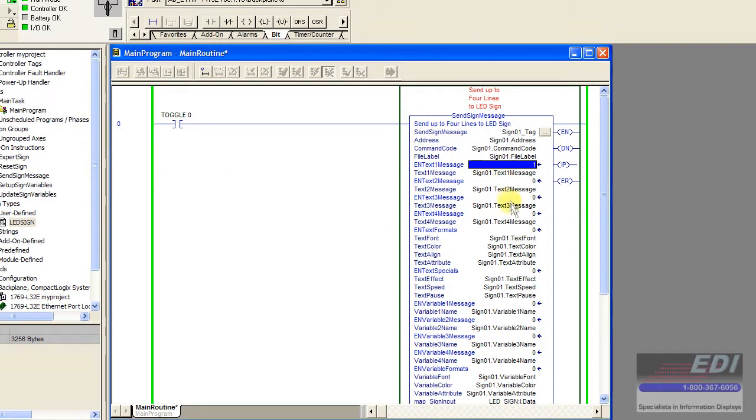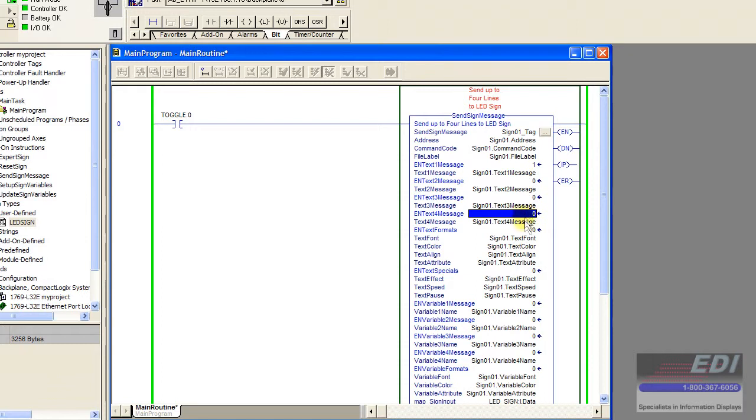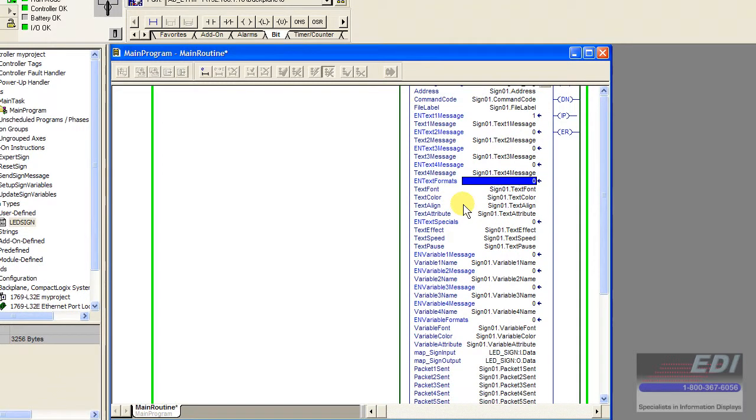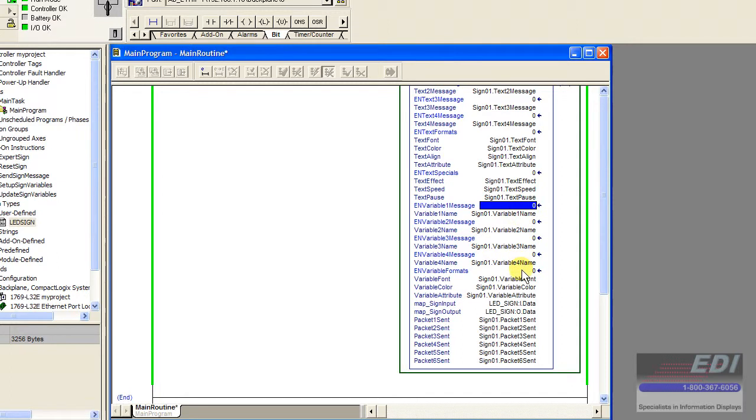You could write ladder logic and only have one block with four messages, then by selecting which flag you want, send a message that way. Or you could have four separate function blocks and send just the first message. In this case, we're going to enable message 1 because we don't have anything in messages 2, 3, or 4. We'll leave text formatting off, special effects off, we don't have any variables, and variable formats turned off.